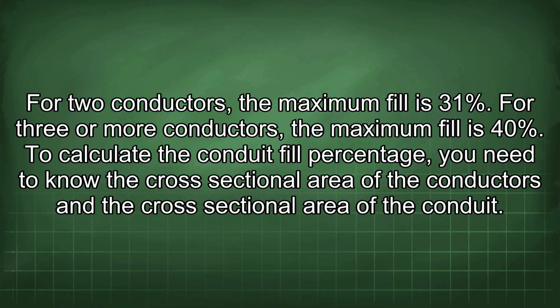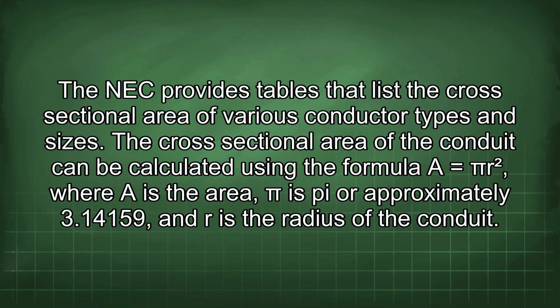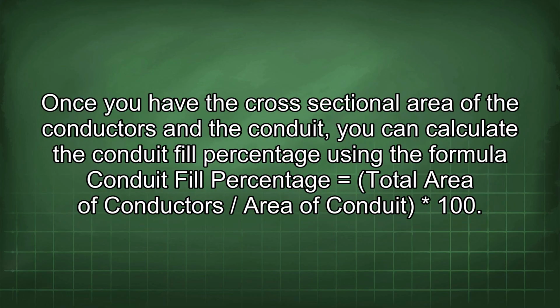To calculate the conduit fill percentage, you need to know the cross-sectional area of the conductors and the cross-sectional area of the conduit. The NEC provides tables that list the cross-sectional area of various conductor types and sizes. The cross-sectional area of the conduit can be calculated using the formula A = πr², where A is the area, π is pi or approximately 3.14159, and r is the radius of the conduit. Once you have the cross-sectional area of the conductors and the conduit, you can calculate the conduit fill percentage using the formula: conduit fill percentage equals total area of conductors divided by area of conduit, times 100.